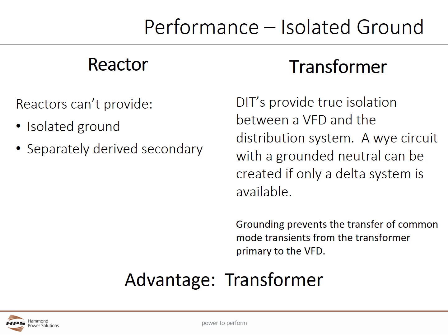Performance with an isolated ground. VFD manufacturers typically suggest that their units be supplied with an isolated ground. Systems such as delta and open delta systems may not have an isolated ground. Even neutral Y systems, especially in large facilities, may have questionable local ground quality. Reactors can't provide either an isolated ground or a separately derived secondary.